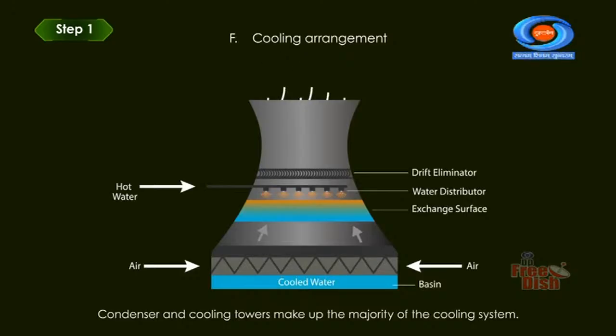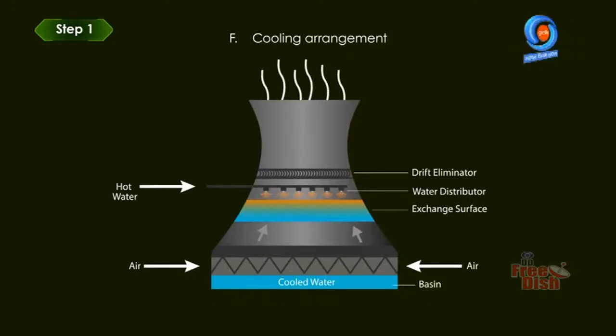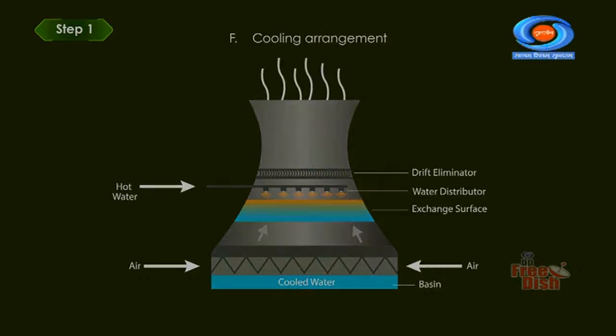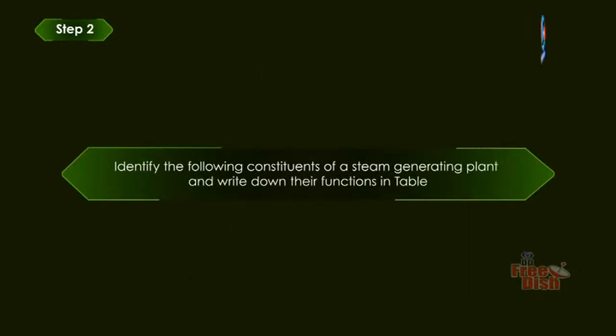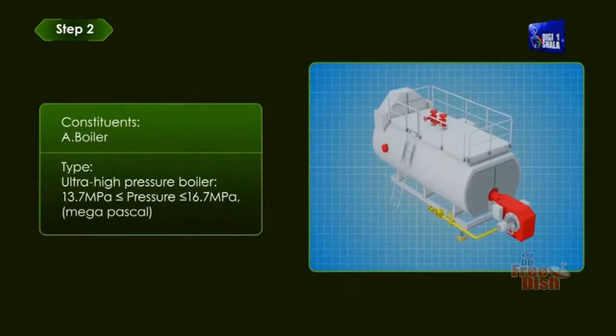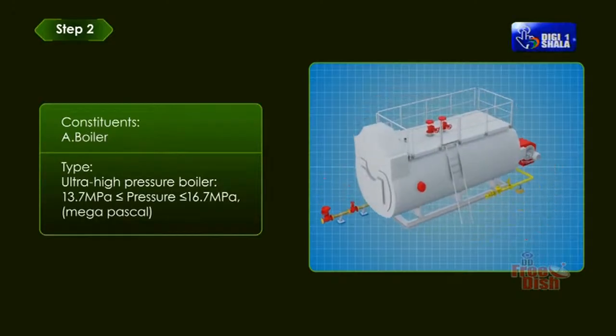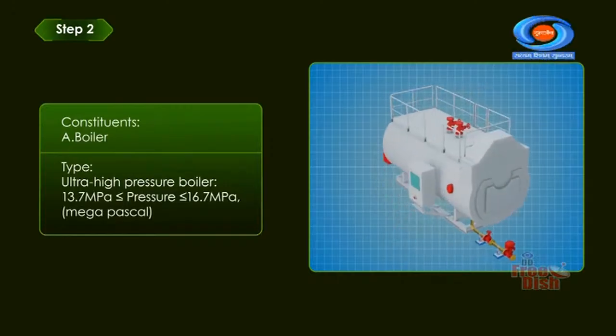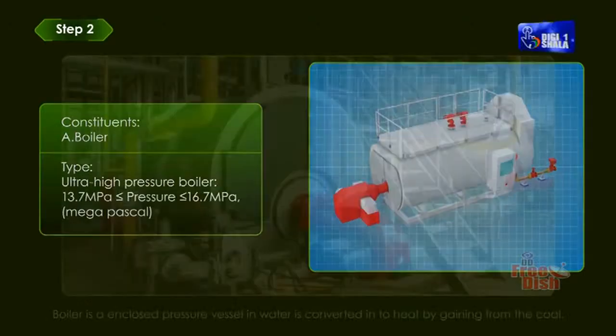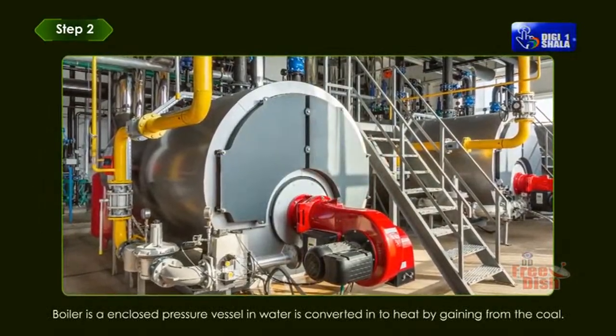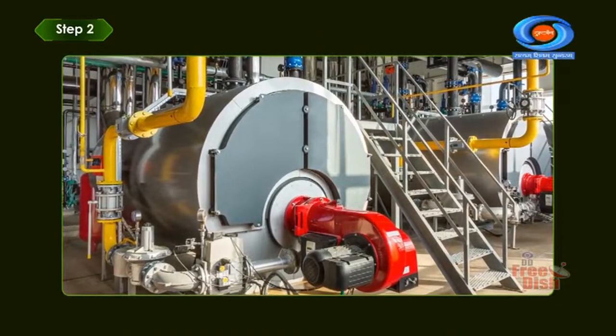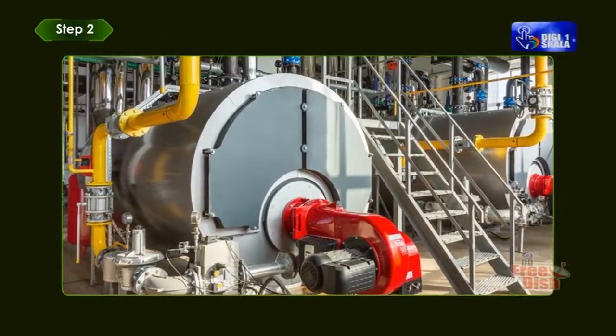F. Cooling arrangement. Condenser and cooling towers make up the majority of the cooling system. In order to increase the power plant's overall efficiency, the condenser is utilized to condense the steam exhausted from the turbine. Step 2. Identify the following constituents of a steam generating plant and write down their functions in a table. Constituents: A. Boiler. Type: ultra high pressure boiler, 13.7 megapascal ≤ pressure ≤ 16.7 megapascal. Function: boiler is an enclosed pressure vessel in which water is converted into steam by heat gained from the coal. Here, combustion takes place at 1300 to 1700 degrees Celsius.